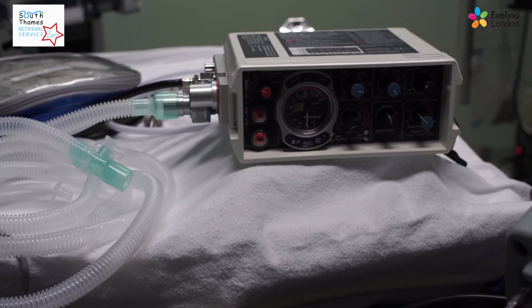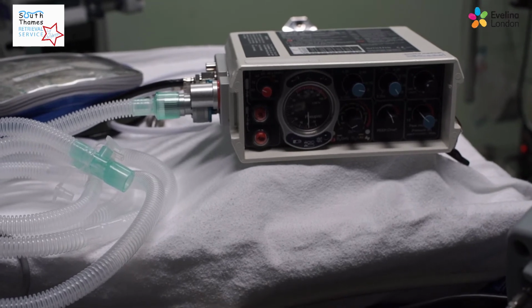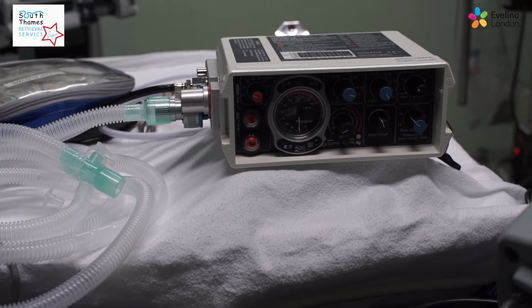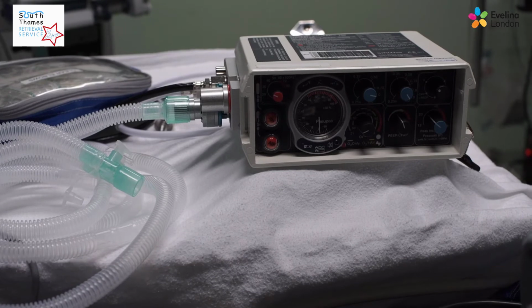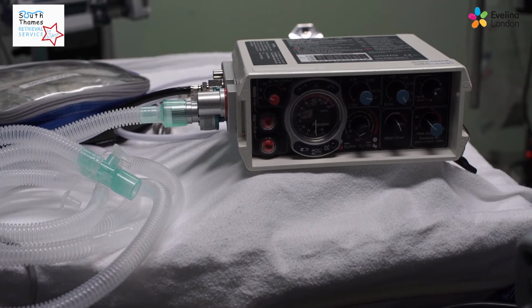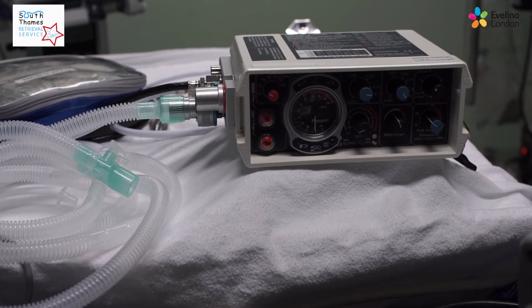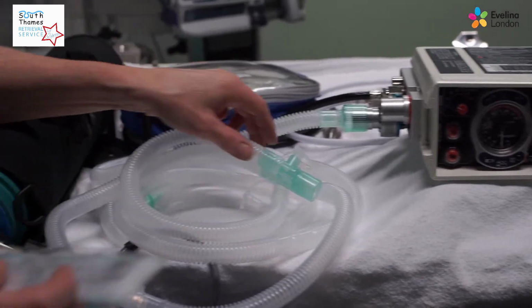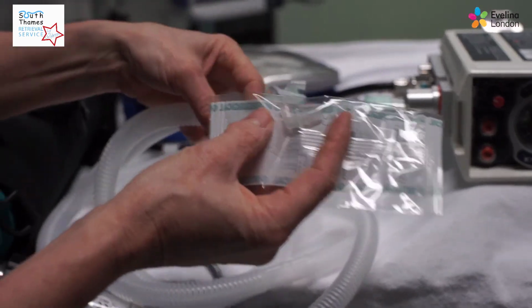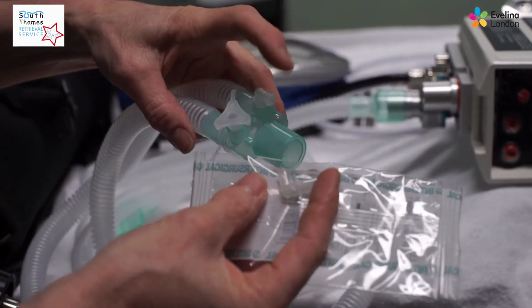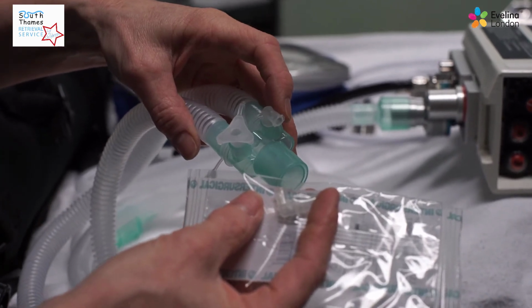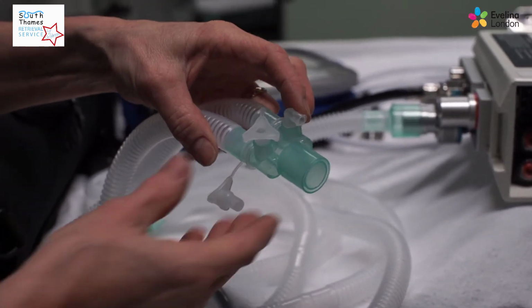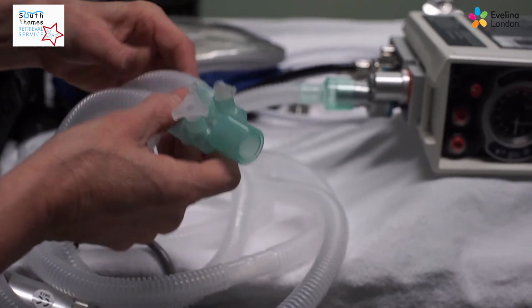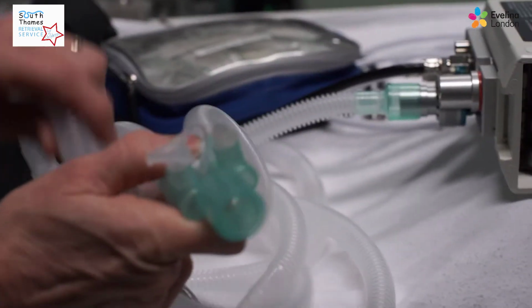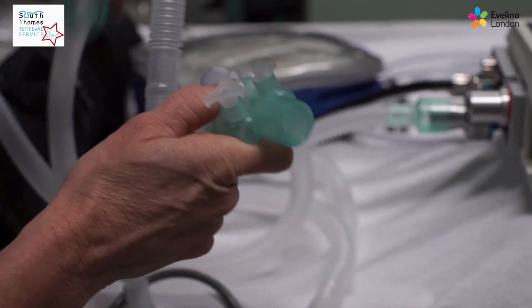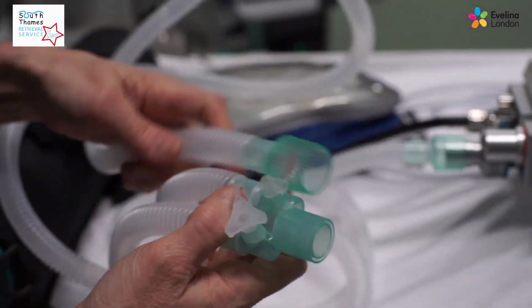Now you're ready to connect the babyPAC to the nitric monitor. To do this, you can only use a babyPAC ventilator for nitric. So you get the babyPAC with the same babyPAC tubing. However, this time it's important to connect a clear elbow onto the expiratory limb of the ventilator circuit. It's also really important to recognise the inspiratory and the expiratory ports of a ventilator, so you connect the tubes to the right part.